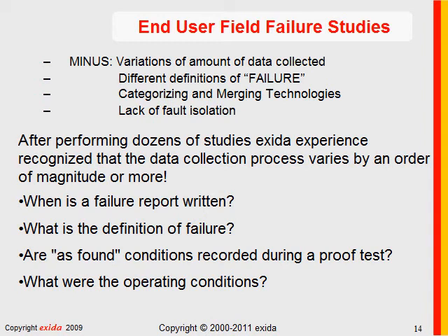The analyst must completely understand the data collection process. The questions one would ask are, exactly when is a failure report written? And what is the definition of failure? Believe it or not, people have very different definitions. Are the as-found conditions recorded during a proof test? A proof test, what's that?